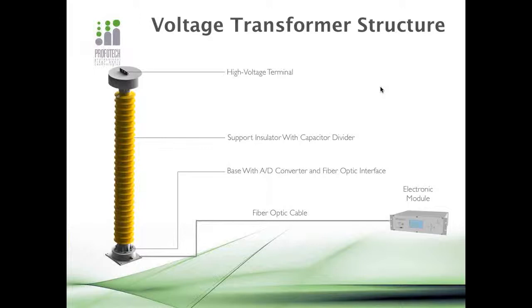That's the sensor part. The voltage transformer is actually, we may say, an electronic optical voltage transformer. It consists of the high voltage terminal and the capacitor divider inside the support insulator. So this column is actually the capacitor divider. What is special about this capacitor divider is that it has the A/D converter installed on the base of this divider. So there is a special small electronic module hidden in the base of this device, and it has the digital output that interfaces with the electronic module.